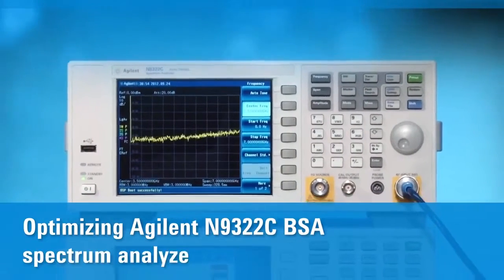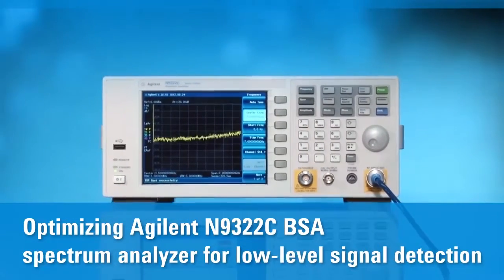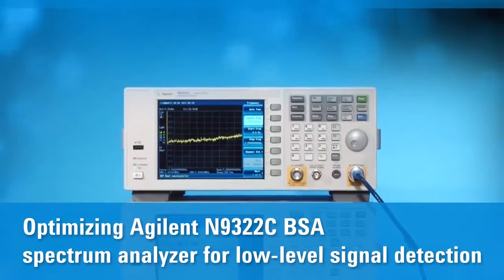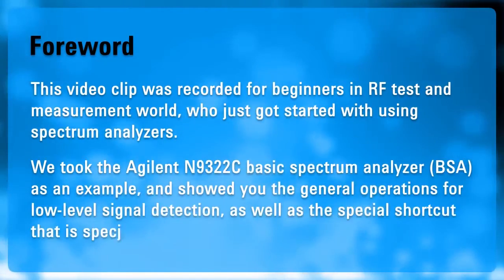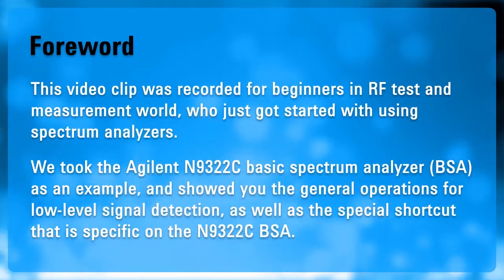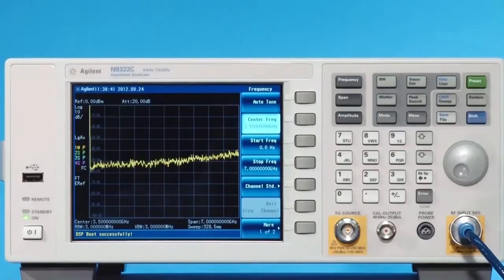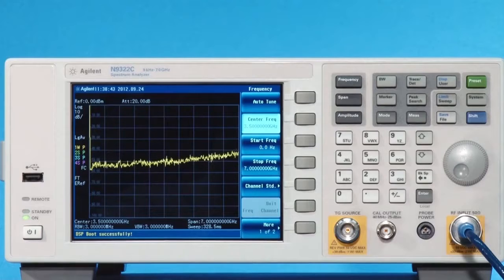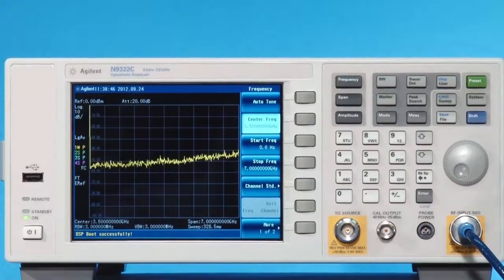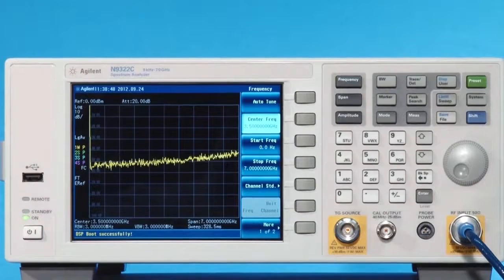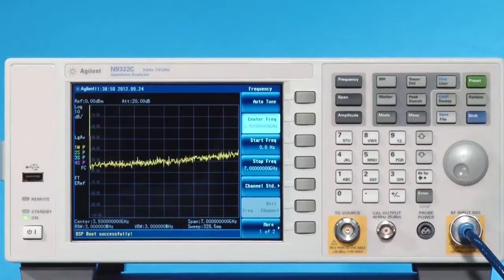Optimizing Agilent N9322C BSA Spectrum Analyzer for Low-Level Signal Detection. A spectrum analyzer's ability to measure low-level signals is limited by the noise generated inside the analyzer. Typically, three adjustments are made to lower the analyzer's displayed average noise level.